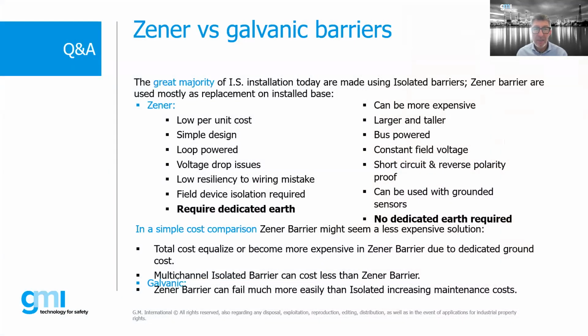This is talking about Zener versus galvanic isolated barrier. There are quite some differences, but the biggest difference is that the galvanic isolated barrier, an isolator, does not require grounding to be safe. It does not require it, and so with that comes the saving and safety and the differences. Yeah, here's the important thing to remember with Zener barriers.